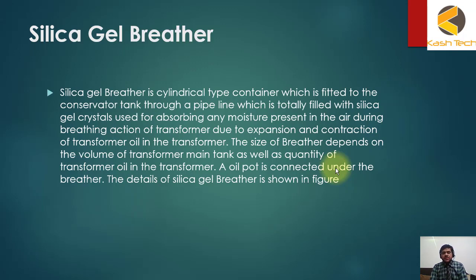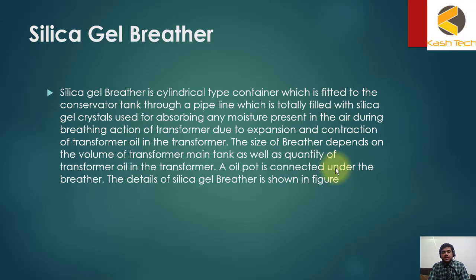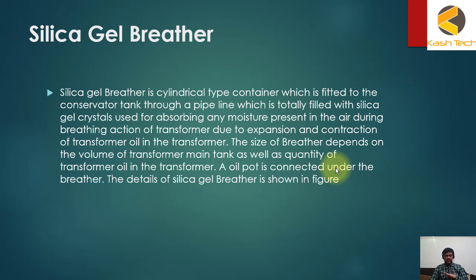Due to expansion and contraction of transformer oil, the size of the breather depends on the volume of the transformer main tank as well as the quantity of oil in the transformer. The conservator tank is basically there to allow expansion of transformer oil. When the transformer oil expands and contracts, it will breathe in or breathe out air — just like breathing.